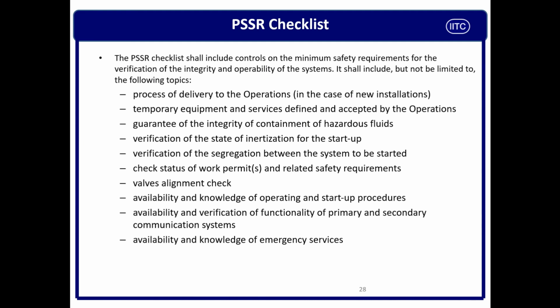Verification of the state of inertization: you need to find out which equipment must be inertized before startup and whether this inertization has been done. Verification of segregation between the systems to be started, and you need to know which system should be started first, in what sequential fashion. This has to be done as a team.